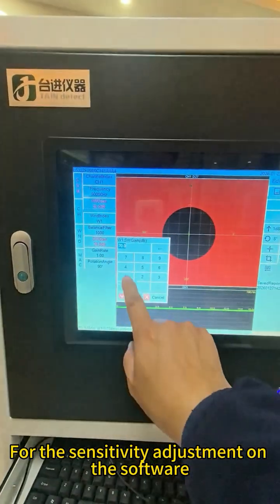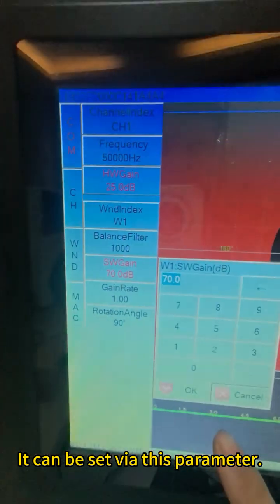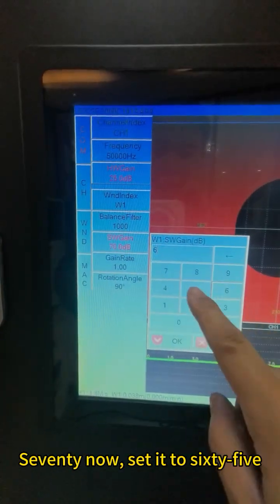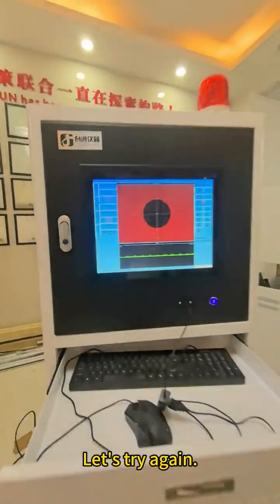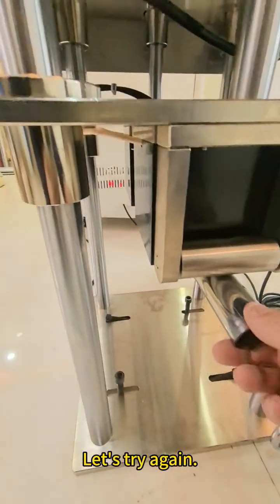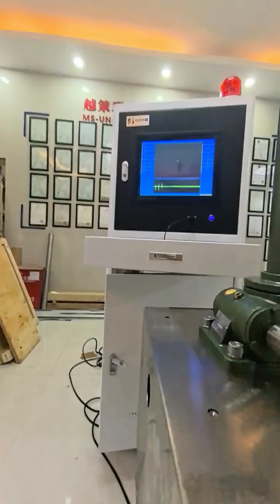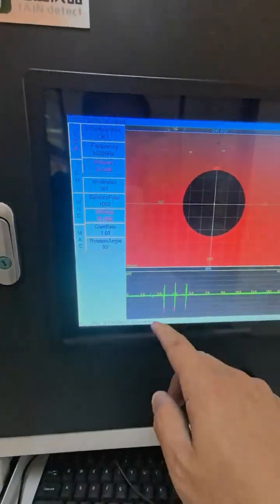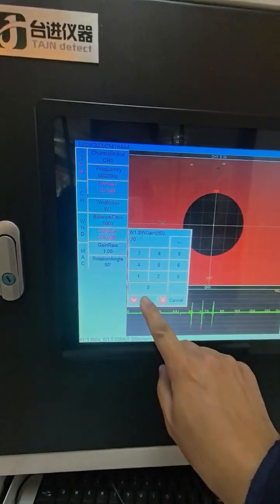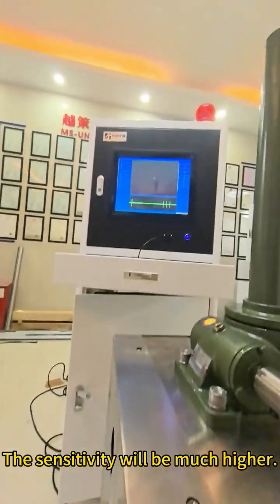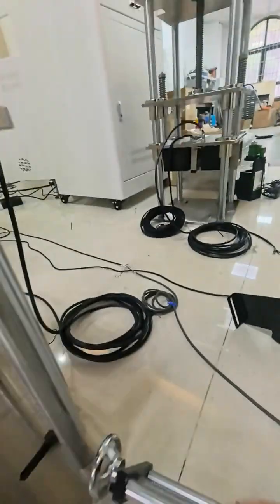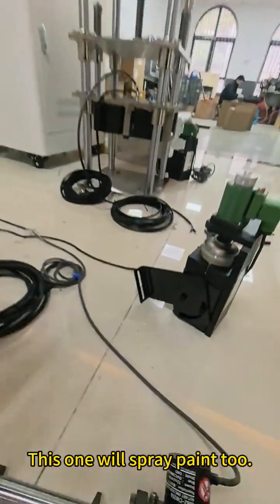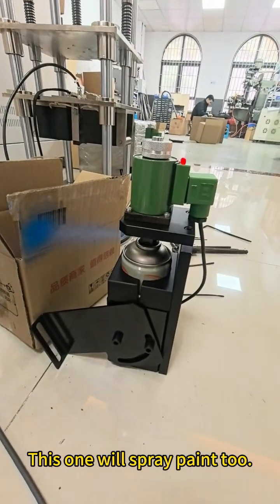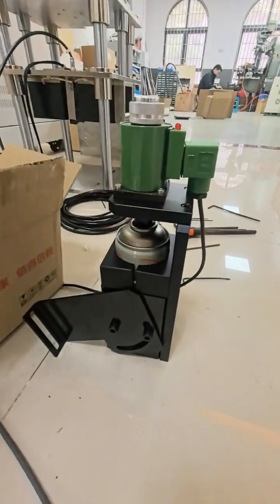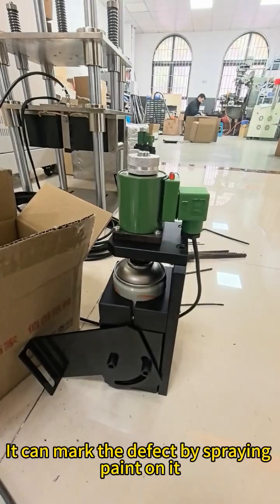For the sensitivity adjustment on the software, it can be set via this parameter. It's 70 now, set it to 65. Let's try again. The signal will become much weaker. Set it to 70 again. The sensitivity will be much higher. This one will spray paint too. It can mark the defect by spraying paint on it.